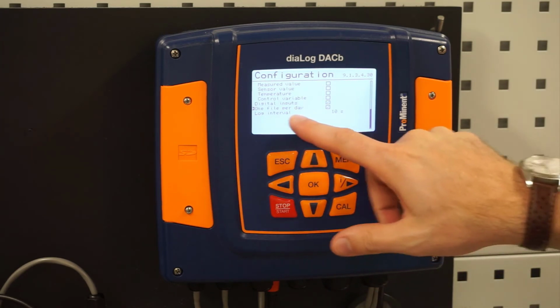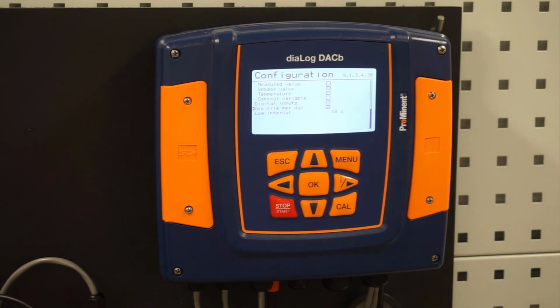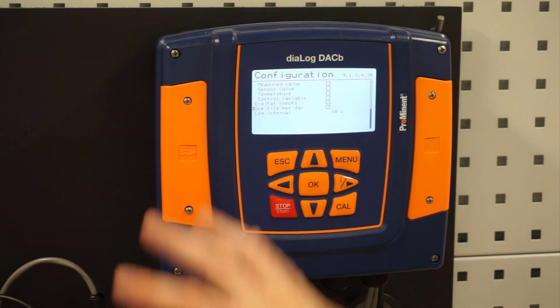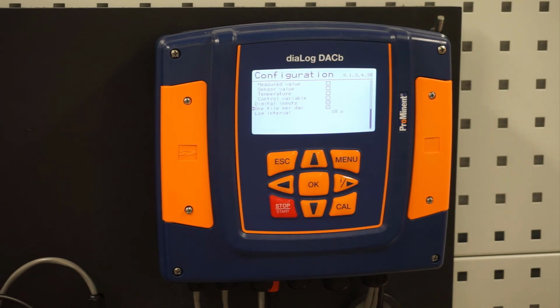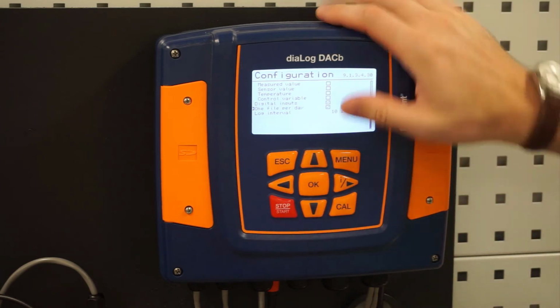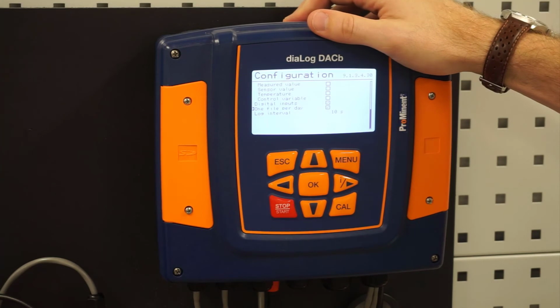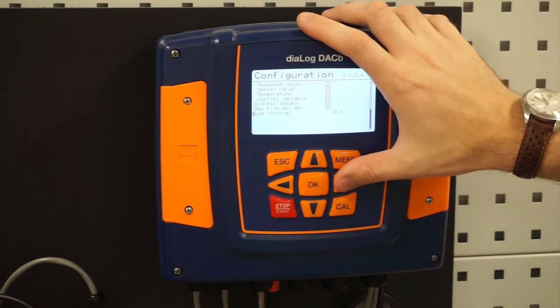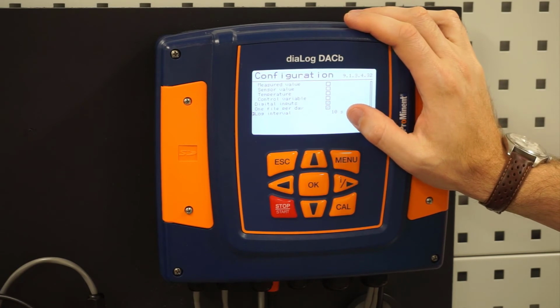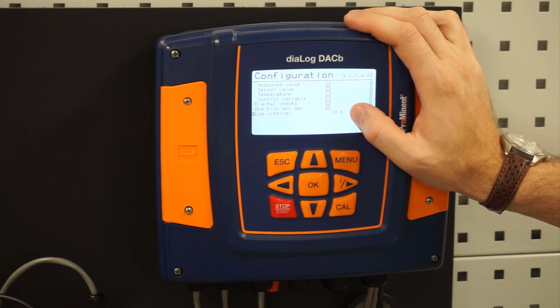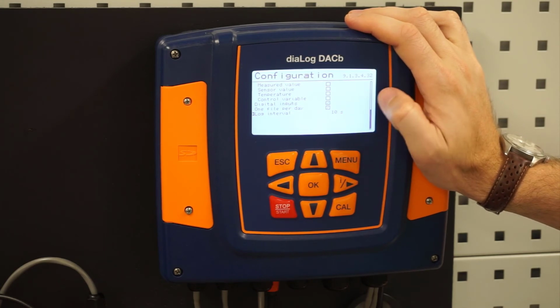You can graph it, you can chart it, whatever you want to do with that data. I will tell you that logging 10 seconds is probably a lot of data. If you decide to do that, don't be concerned about the size of the SD card in there. Even logging for 10 seconds, creating 1 file a day, that is still going to be enough size of that SD card to get you years and years of data. So I wouldn't be concerned even logging at 10 seconds of overloading that SD card with too much data. 30 seconds or 60 seconds may be more of a realistic time to log, because otherwise every 10 seconds you're getting a lot of data out of here.